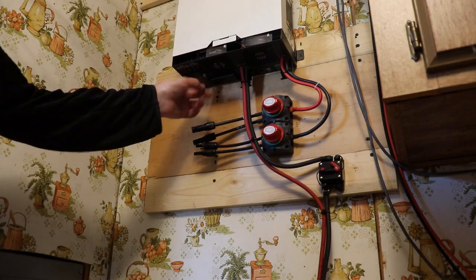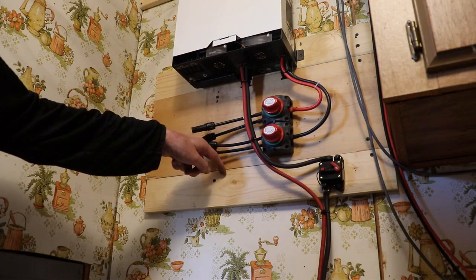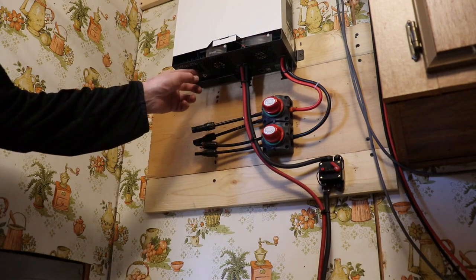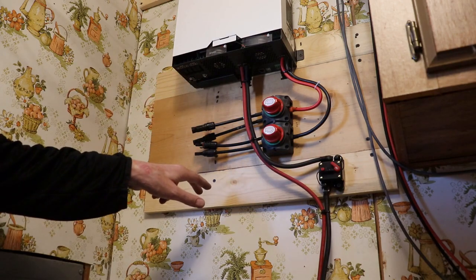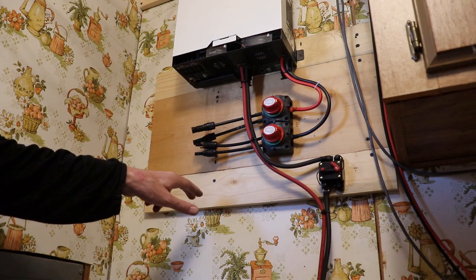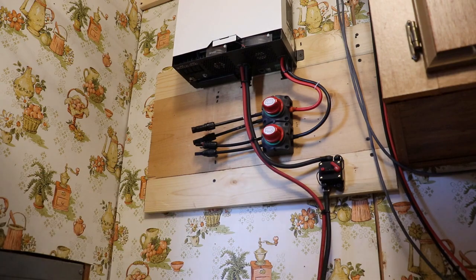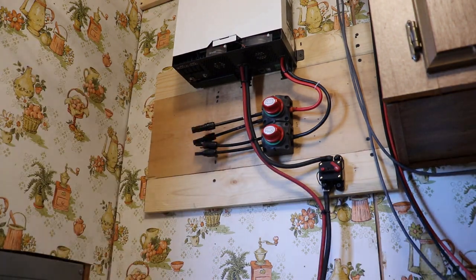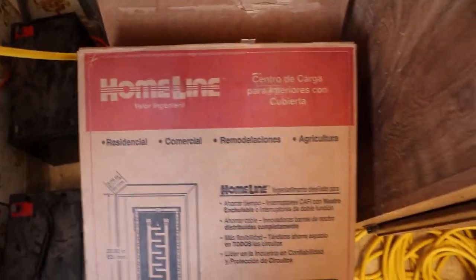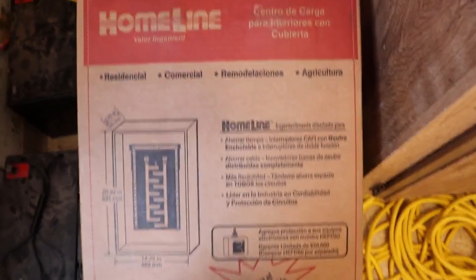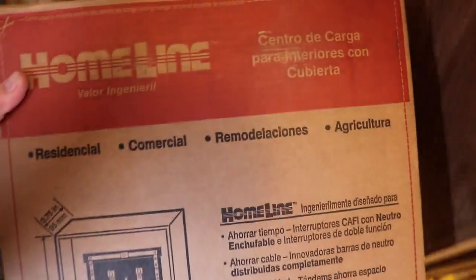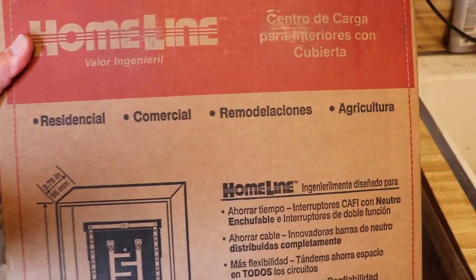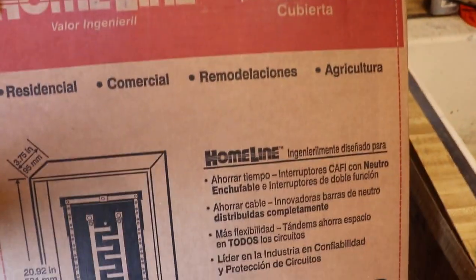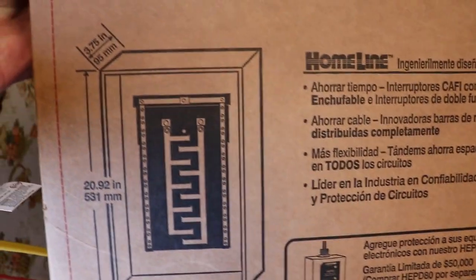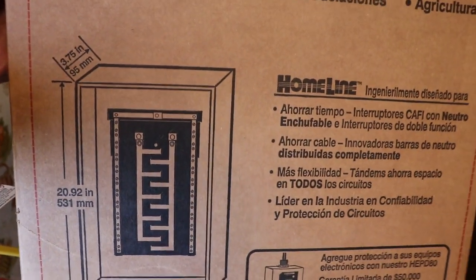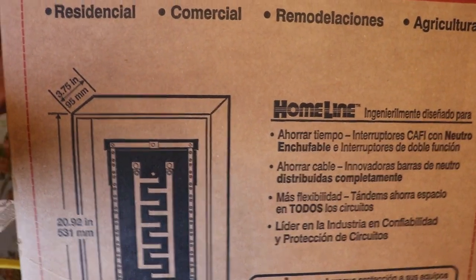I'll run the ground panel down, and run the two wires in on the neutral and the hot wire to create a single phase with circuit breakers in our electrical box. The next step is to put this box in, for residential use. It has a main shut-off switch, it's 100 amperes, could easily be used in the cabin, and it's expandable as you expand units.